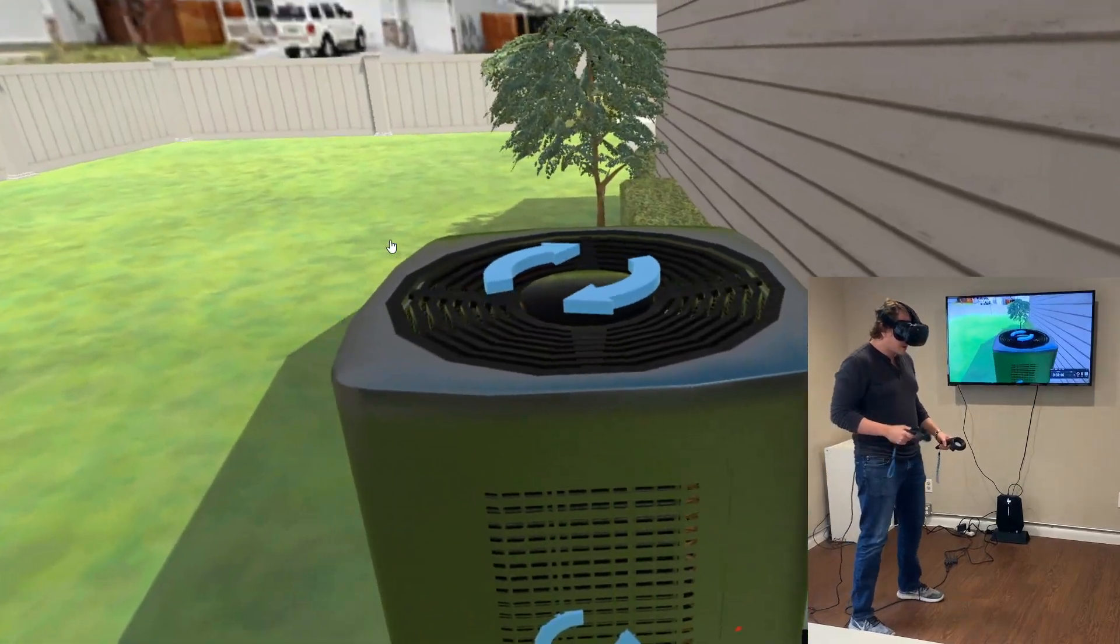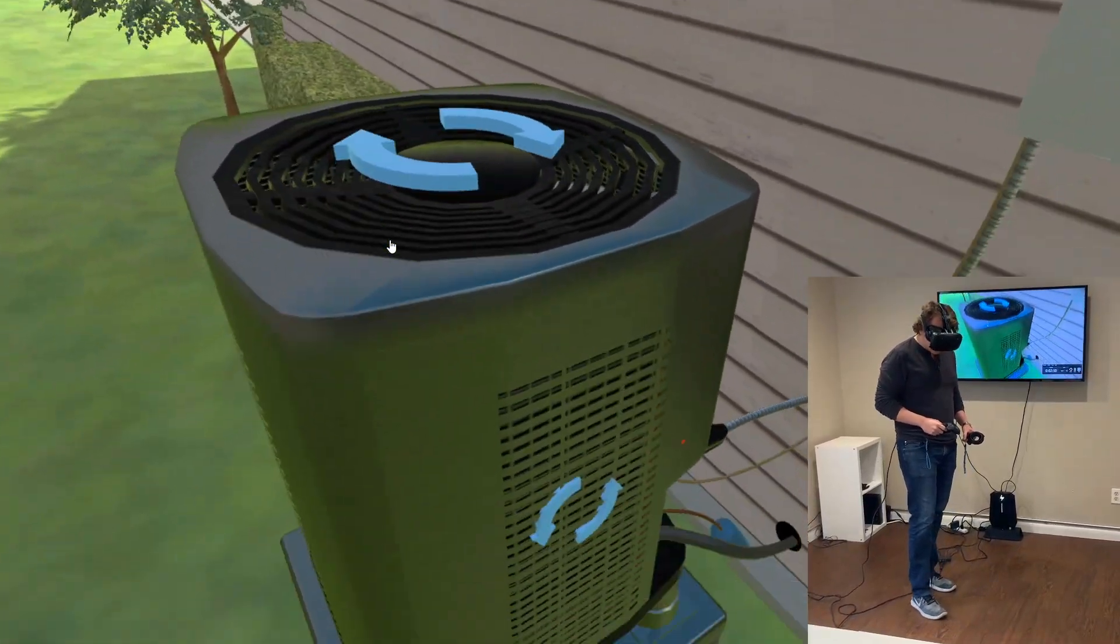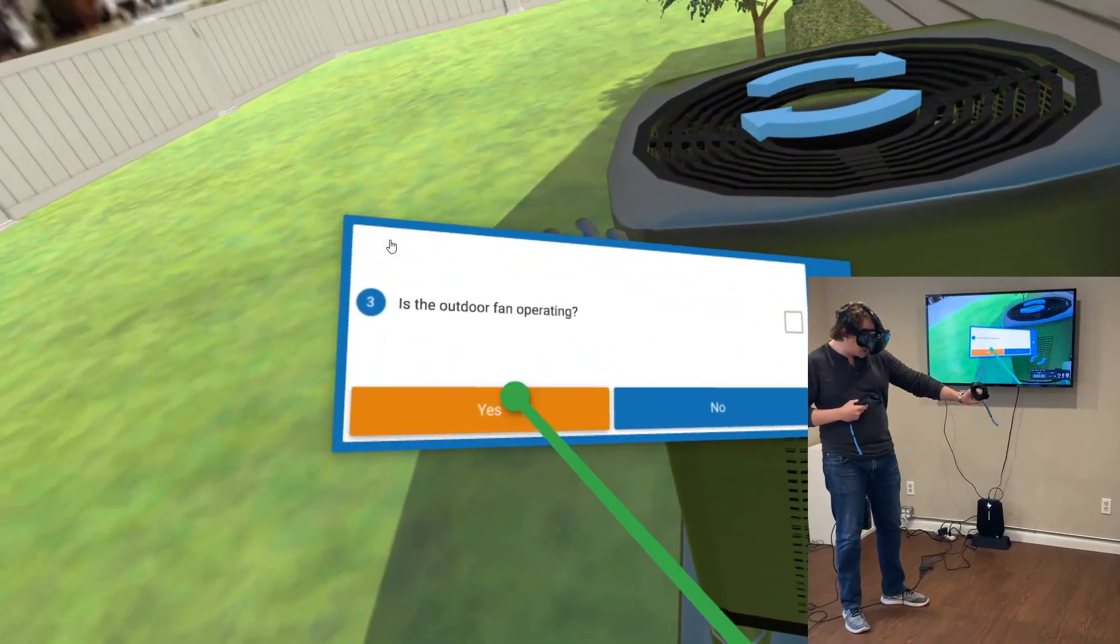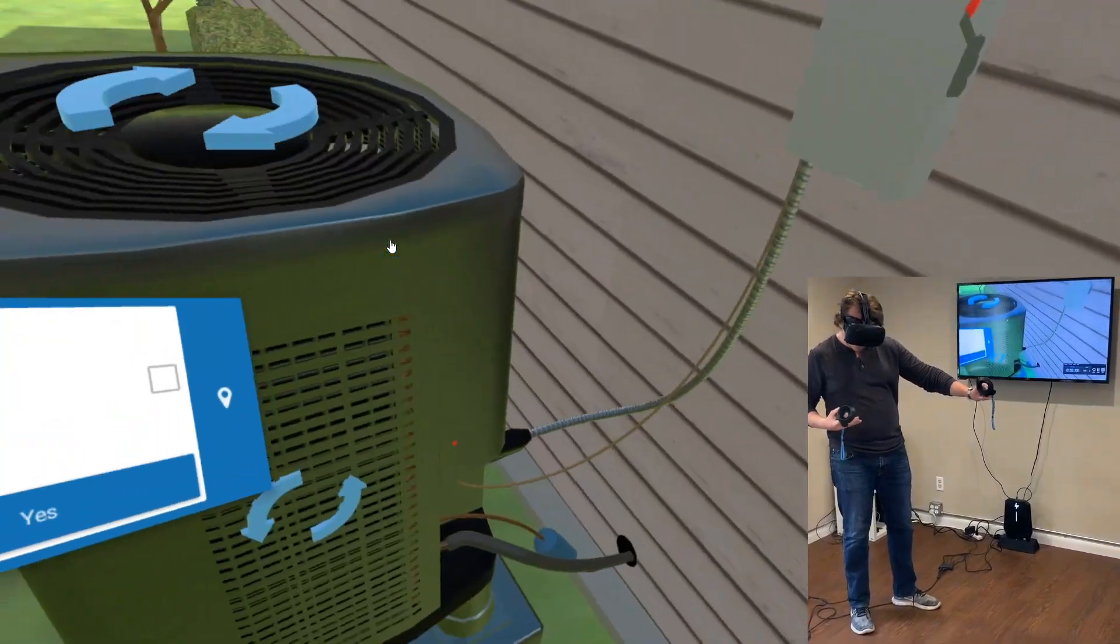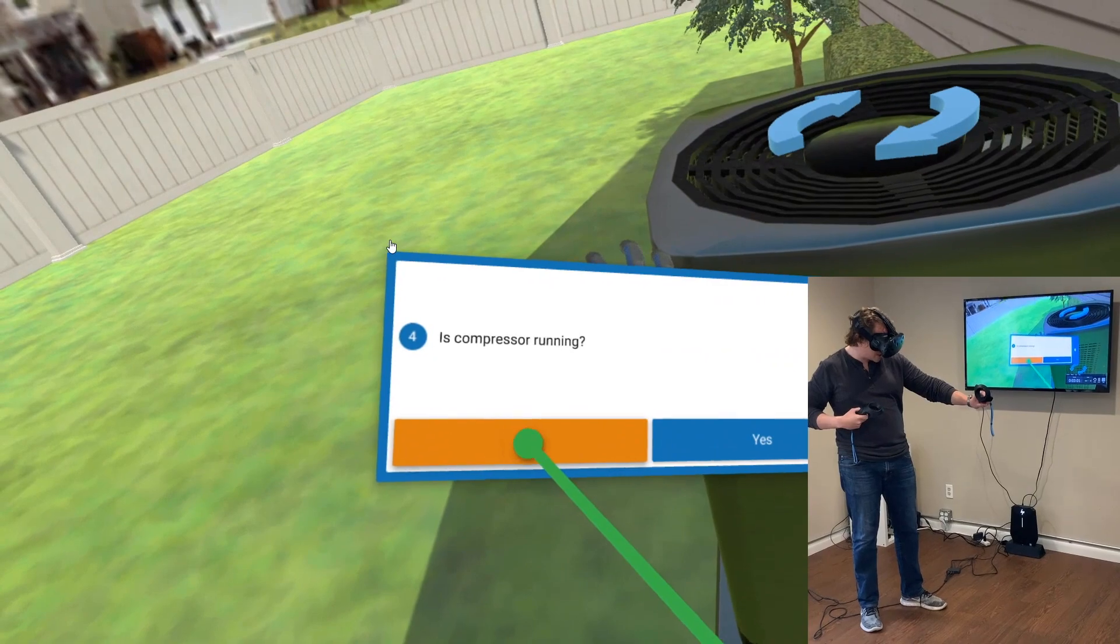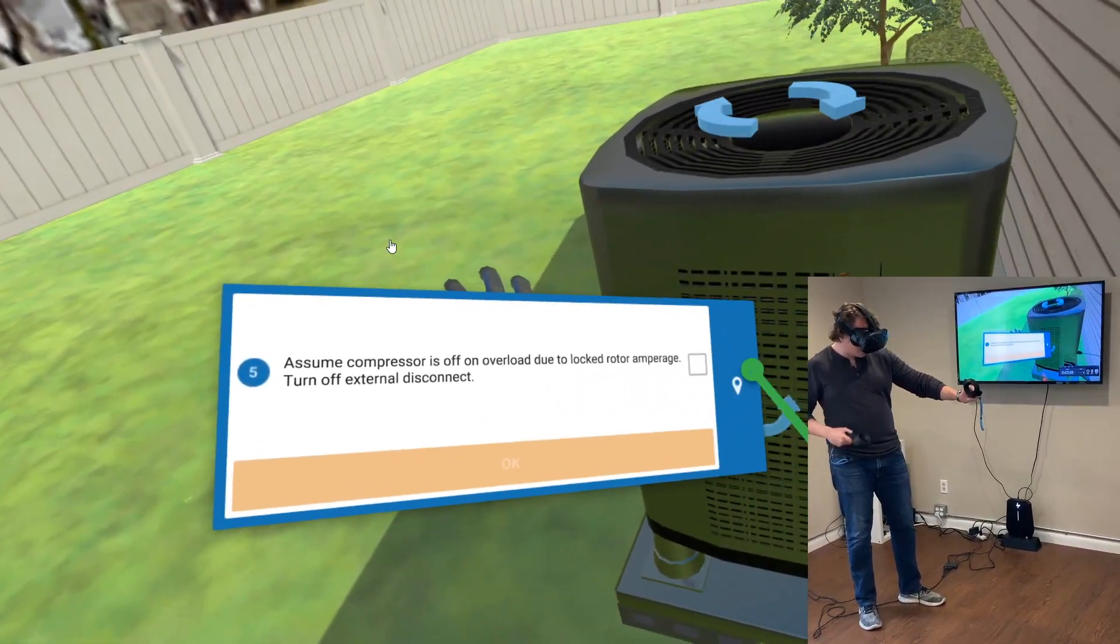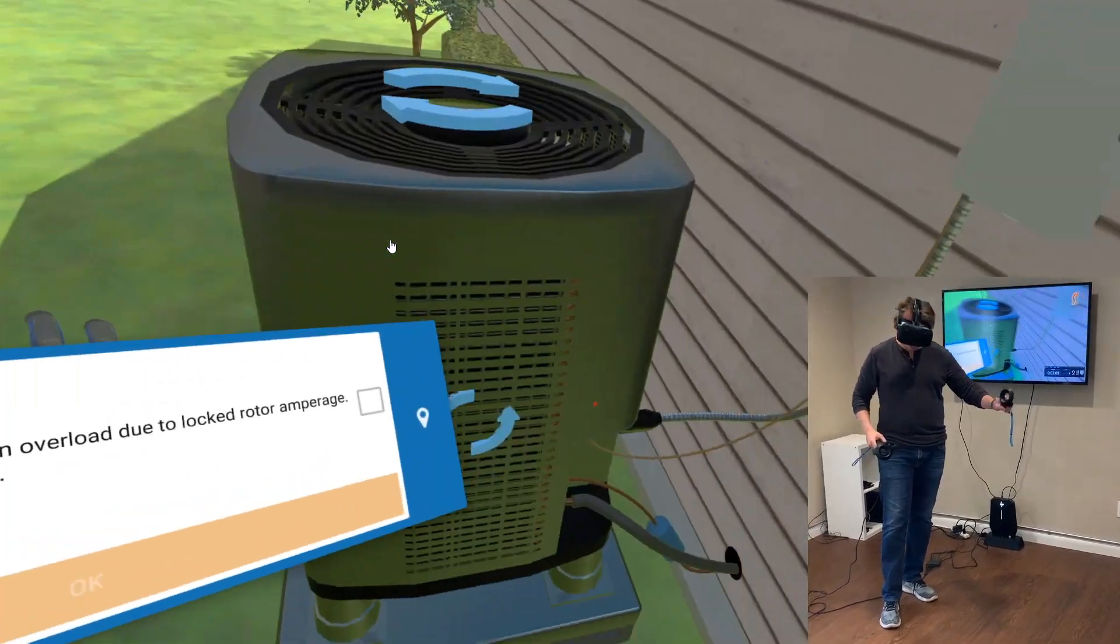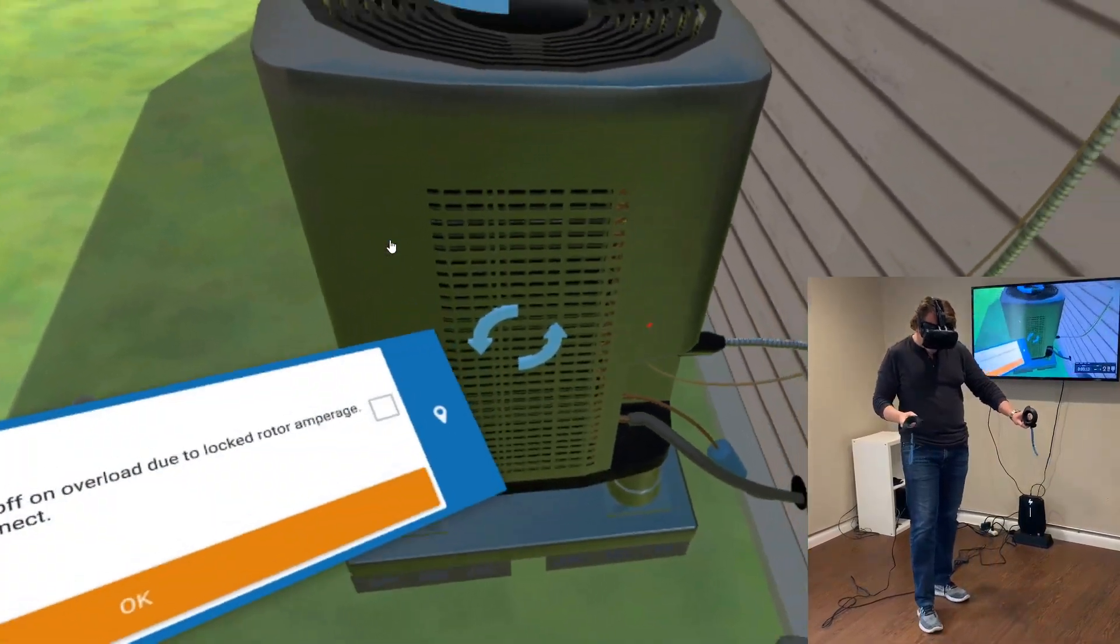Let's go check out the outdoor unit. I can see visually that the fan is running, but I'm thinking there's going to be an issue with the compressor. Is the compressor running? I've done this so many times I'm now getting good at what I need to be checking. Actually no, the compressor is off on overload due to locked rotor amperage. Turn off the external disconnect, so that's leading me to drop the disconnect here.